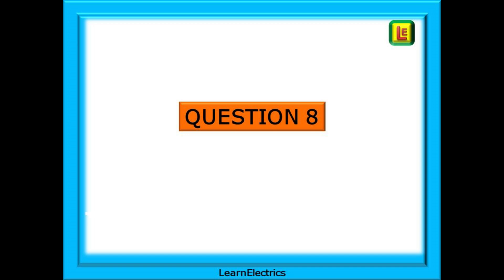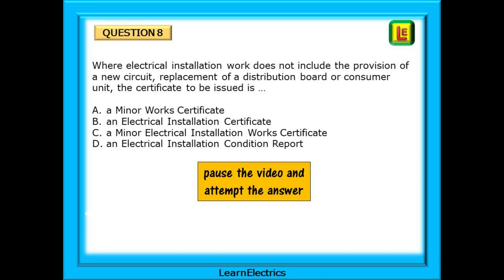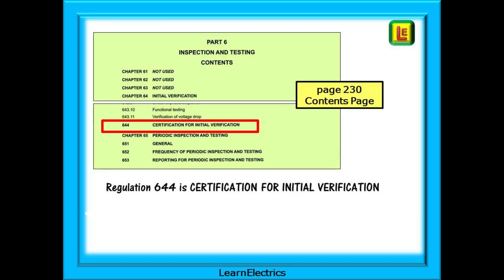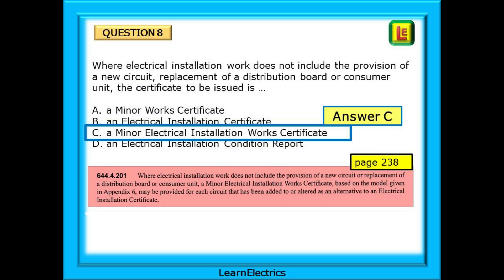Question 8: where electrical installation work does not include the provision of a new circuit nor the replacement of a distribution board or consumer unit, the certificate to be issued is — and four choices. This is installation work so the answer is in chapter 64. Looking at page 230, we can see Regulation 644 — certification for initial verification. Regulation 644.4.201 on page 238 gives the correct answer: Minor Electrical Installation Works Certificate. Answer C. Answer A looks plausible but is not exactly what it says in the regulation. It must be Minor Electrical Installation Works Certificate — answer C.